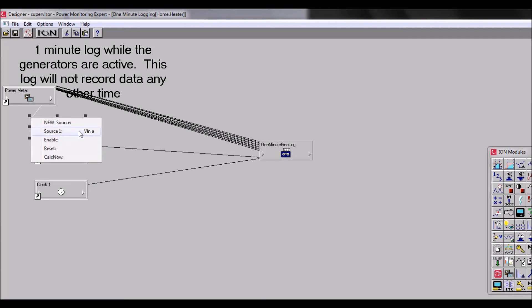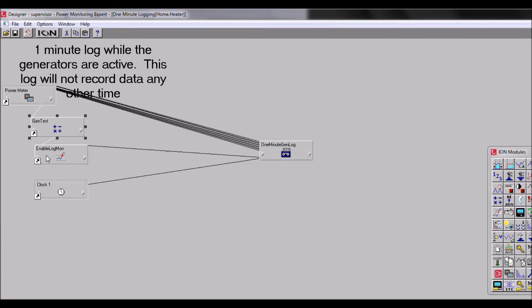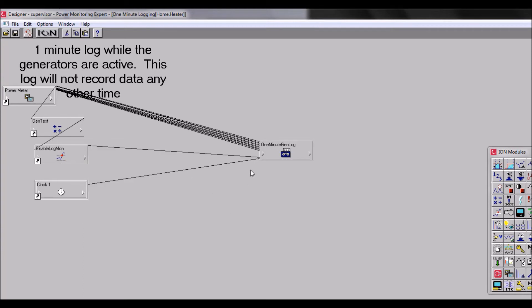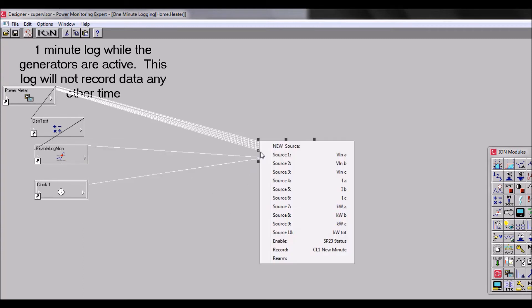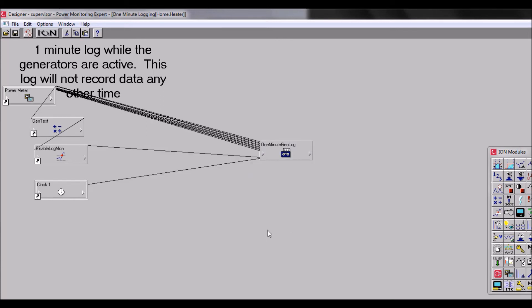So this is a voltage. All we're doing in this is just testing to see if the voltage is above zero. Then if we go from the arithmetic module to the setpoint module, the setpoint module is converting that numeric number into a boolean status so that we can enable the data recorder when the generators are running.